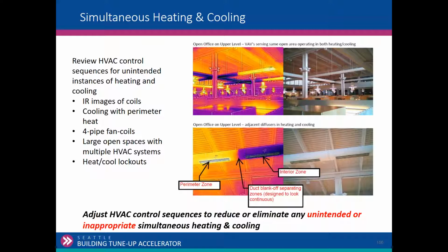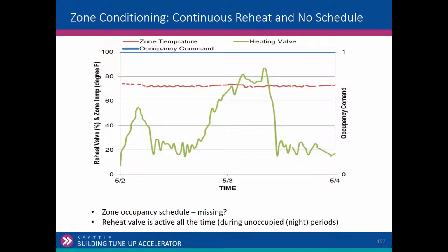So anyway, if you obviously see situations where there's simultaneous heating and cooling, we want you to review those sequences for unintended issues, where you've got adjacent zones with one zone set at 68 and this one set at 75 and they're fighting each other. That would be an area of maybe making some recommendations, taking an average temperature, increasing the deadband between the two, resetting the 68 up and the 75 down, something like that. For any unintended or inappropriate simultaneous heating and cooling.